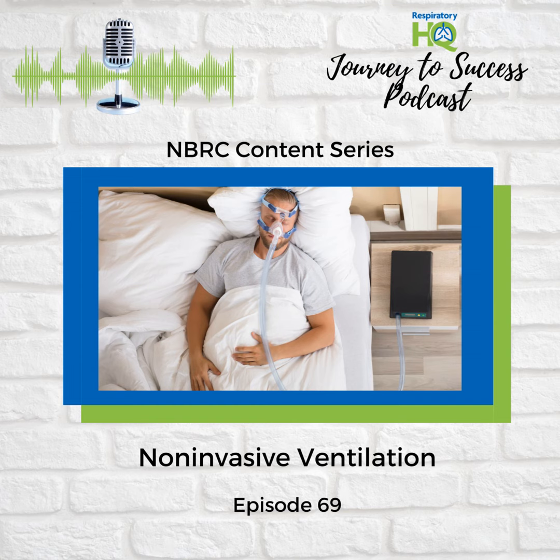What about adjusting BiPAP once it's running? You've got 2 pressures to play with. Right. A key concept here is the difference between IPAP and EPAP. We call that the delta P, or sometimes just pressure support. Delta P, the gap between the 2 pressures. Exactly. And that delta P is what primarily determines the amount of ventilatory assistance, how much CO2 is removed.